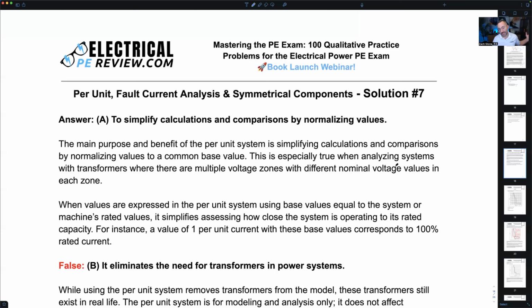And depending on the customer, we might step it down several times. If it's just a residential customer, like right here in my house, then it's just being stepped down once. It's being stepped down by the transformer on the pole outside my house to split phase 120, 240. But if it's a big customer, a big commercial fabricator, big industrial plant, maybe it's a mining location, you could have everything from 13.8 kV, 2400, 4160, all the way down to 480, and then all the way down to 120.